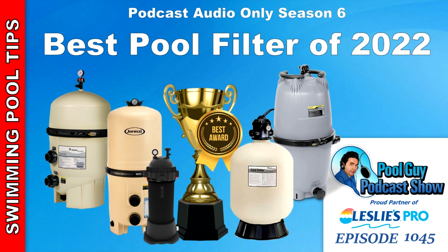Other than that, the Quad D filter would be my first choice when replacing your DE filter. And I'll just add to that before moving on to my other DE filter recommendation. The cartridges seem to last a lot longer than the grids on the Quad D filter. They have bands on them similar to a cartridge filter, and once those start to break and the pleats kind of separate, then you have to replace them. But as far as having holes in them or anything like that, I haven't had that kind of issue. So they seem to last longer than the grid type filters.